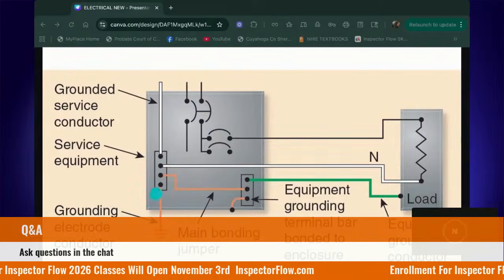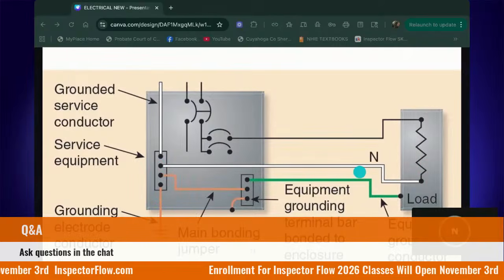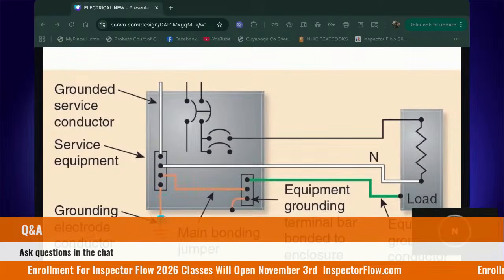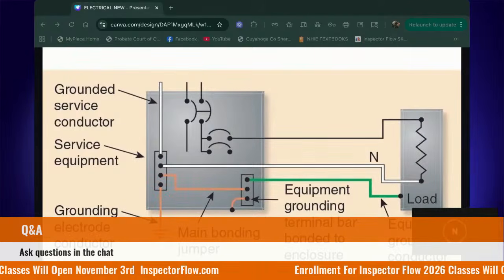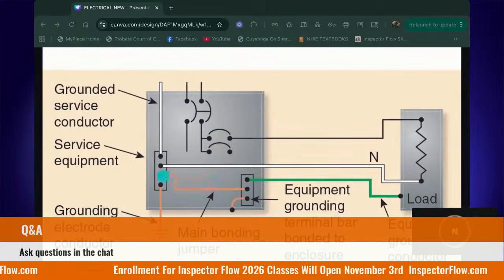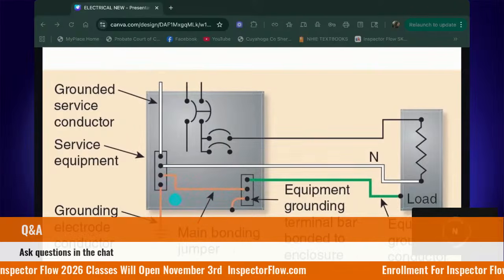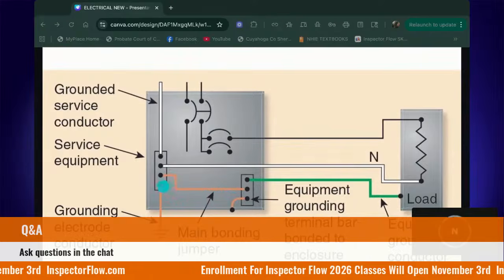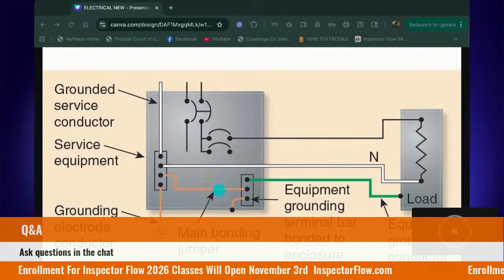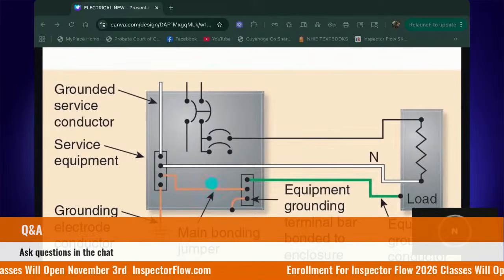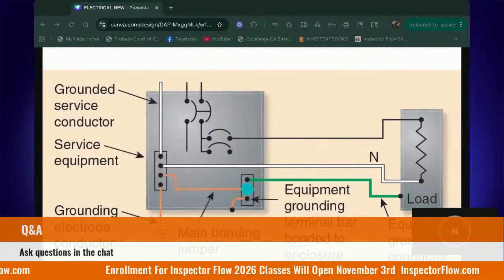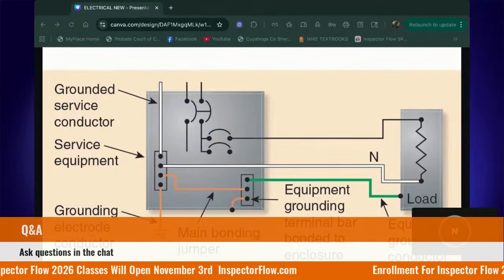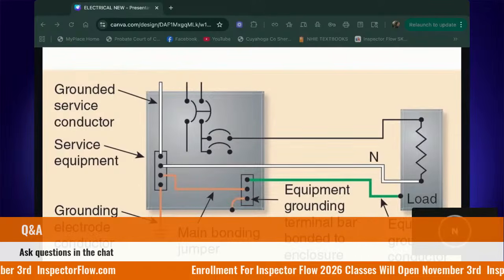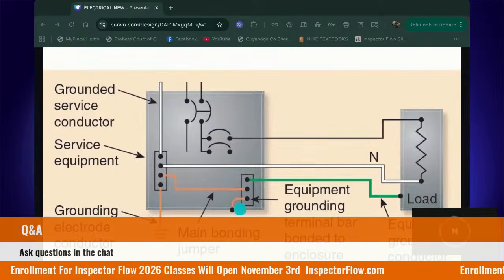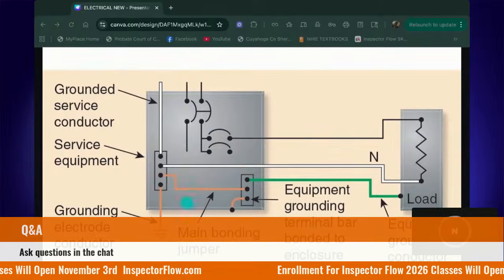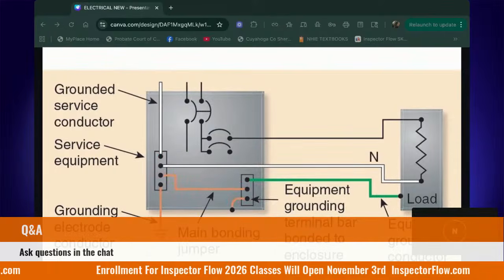Now, if the current is supposed to be coming back here and it can't for some reason, there is a path or a connection to ground. Then this orange bar here is the main bonding jumper that's inside the service panel. This is what bonds the neutral bar to the ground bar. And it's bonding both of these to the actual enclosure, because this is metal too. It could become energized. This is why you've got to be careful, because if something is going wrong and you reach out and touch the panel, just the panel, the dead front, it could potentially be energized. So the bonding jumper is connecting my neutral and my grounding bar.